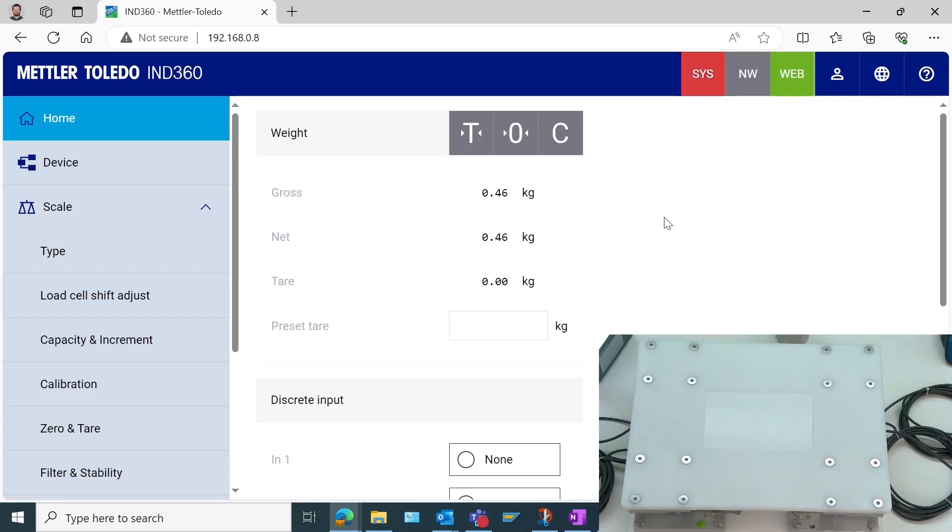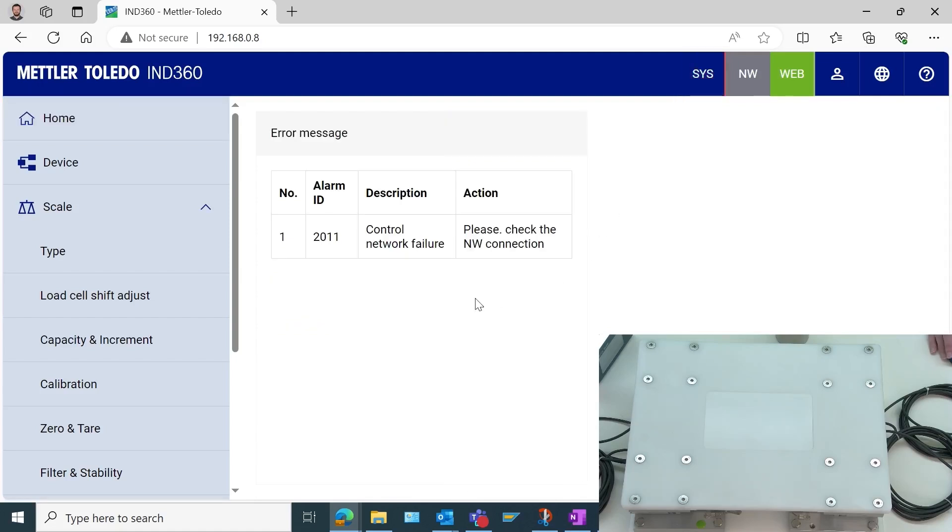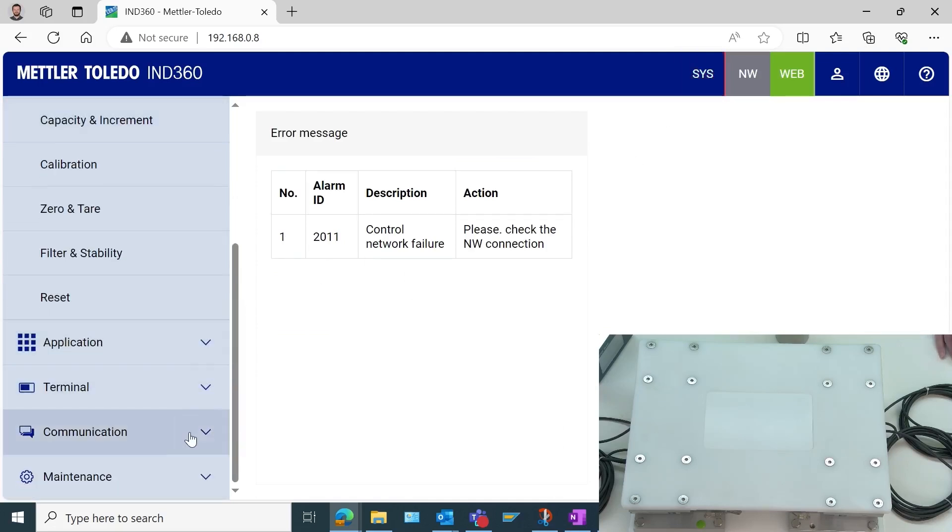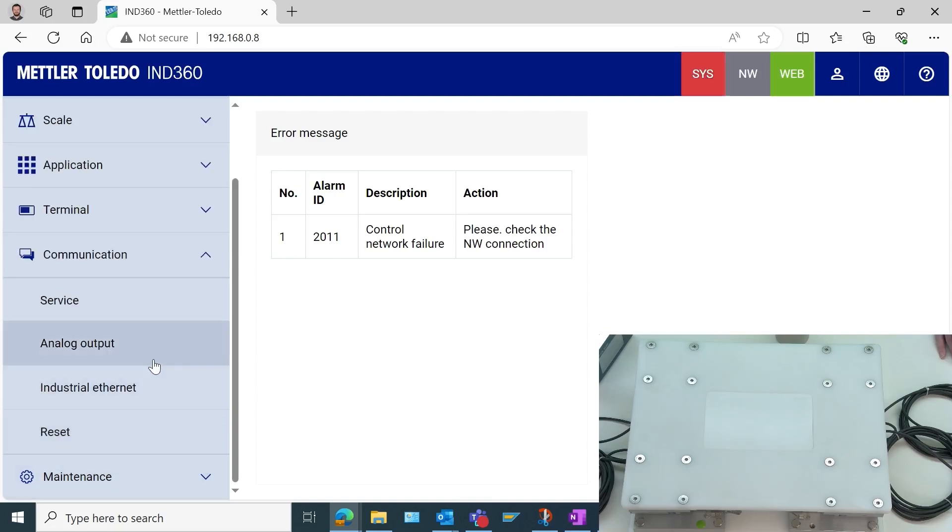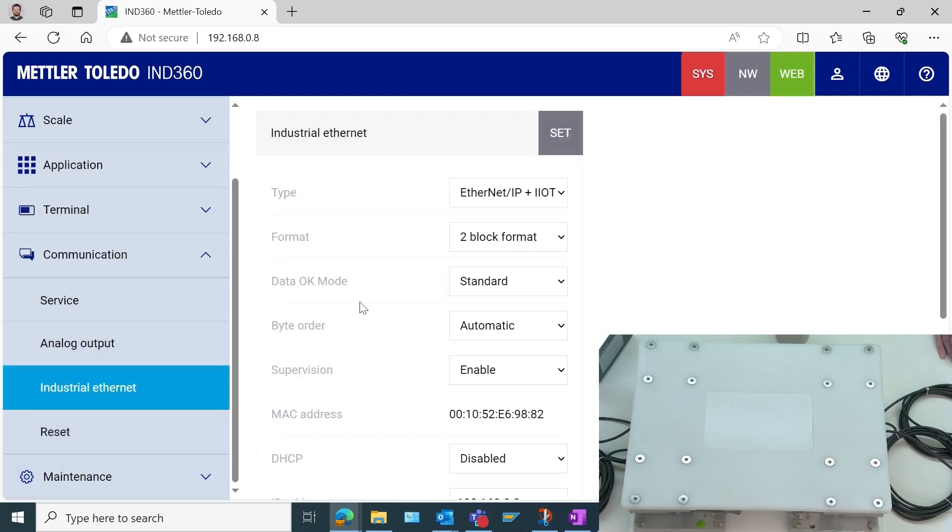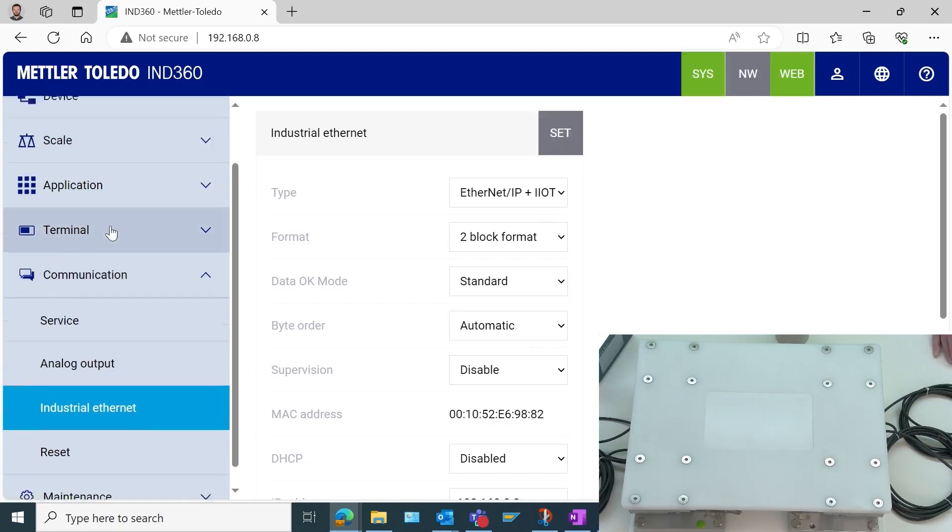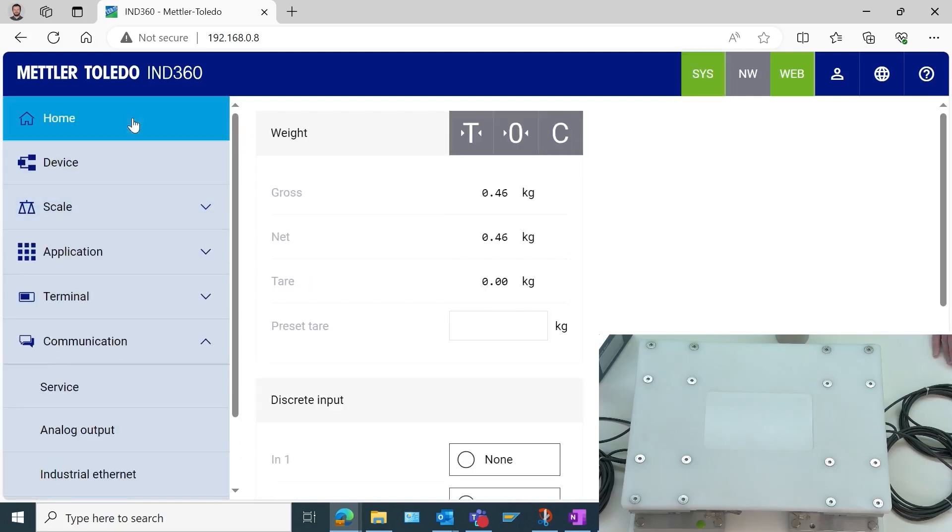First thing I notice here is I've got a flashing red light, which means I've got an error. This is very common to see. This is telling me that I don't have a PLC connected. So if you do have a PLC in your system, feel free to leave this enabled. But for our video, I will go ahead and disable this quickly by going to supervision and disable. Now we see that red light has gone away.